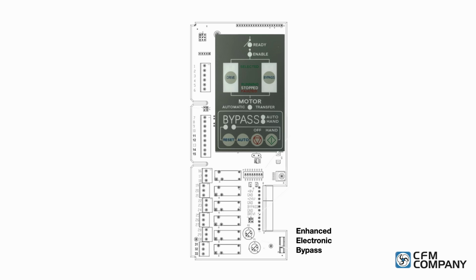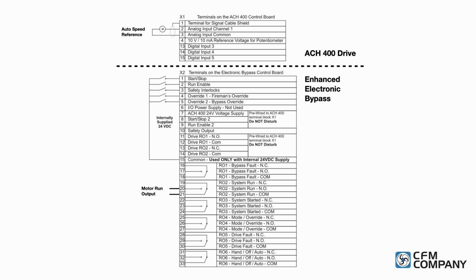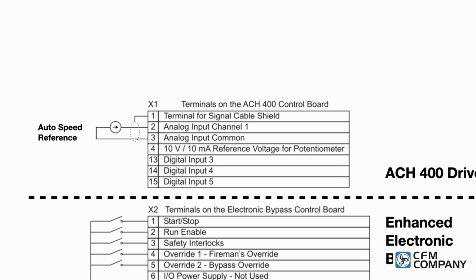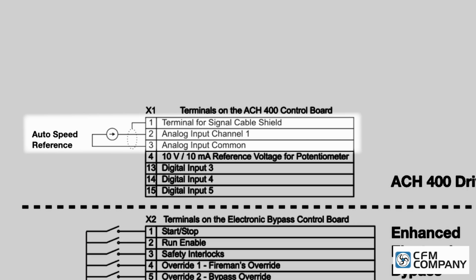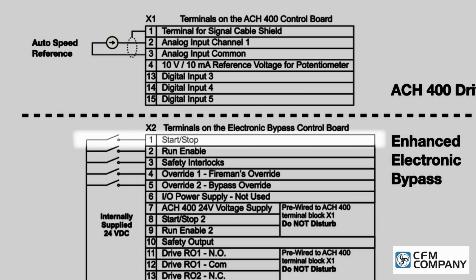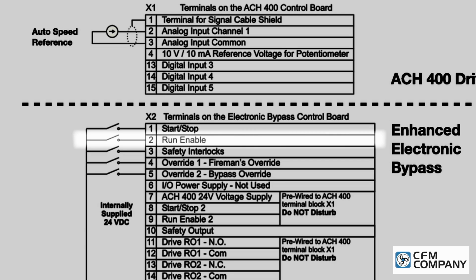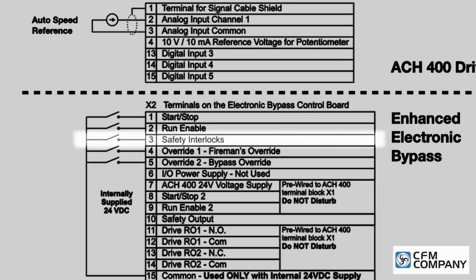Next is the Enhanced Electronic Bypass Control Board, EEBP. The frequency reference is landed on the analog input 1 terminals on the drive. On the bypass control board, terminal 1 is the auto start-stop command. Terminal 2 is the run enable, typically used for a damper end switch. Terminal 3 is the safety interlock, used for field-installed safety devices wired in series.